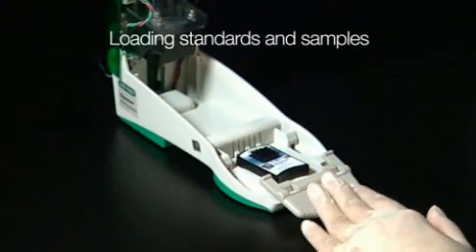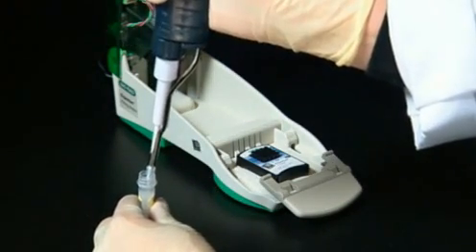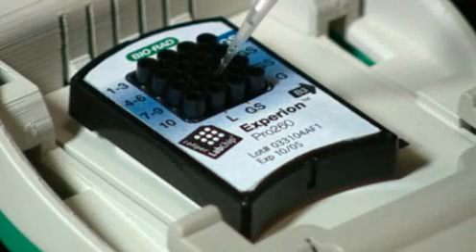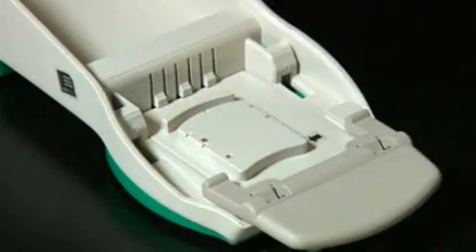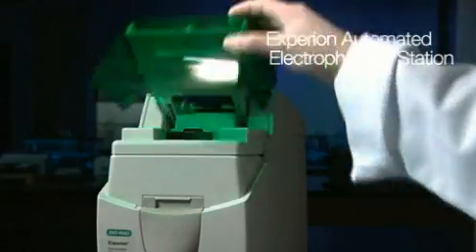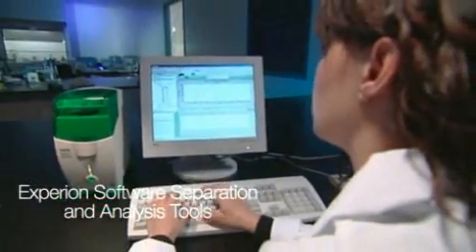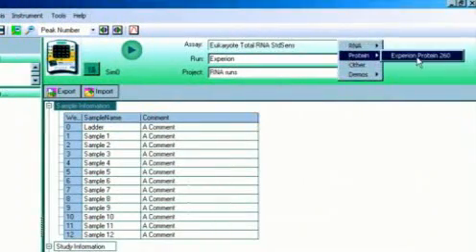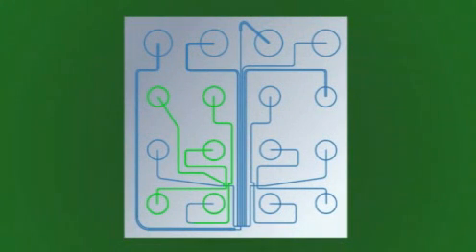Once the chip is primed, it is ready to have standards and samples loaded into the remaining wells. The chip is then placed into the automated electrophoresis station, and the translucent lid is closed before beginning the process. Using Experion's comprehensive software, the appropriate analysis is selected. The separation process then begins by activation of the internal power supply, which applies a voltage to the sample inside the loading well through 16 platinum pins on the electrode manifold, located inside the electrophoresis station lid.